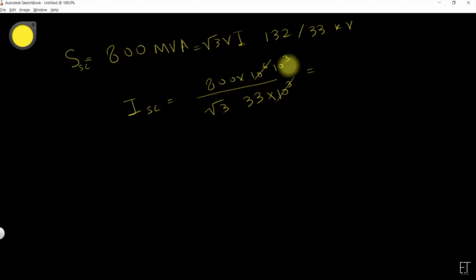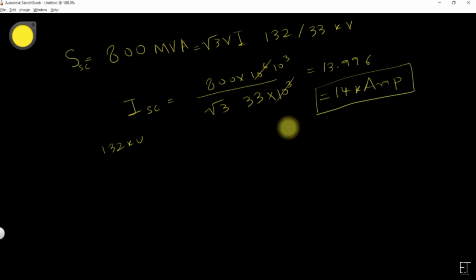So it's coming as 13.996, or we can see it's equal to 14 kiloamperes. So you can see here the short circuit level at the low voltage side is coming as 14 kiloamperes. It means that if you are supplying 132 kV at the HV side and the LV side is short circuited, then this much current will be flowing through the low voltage side.